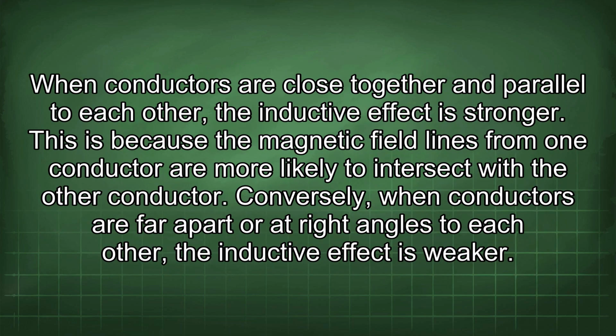When conductors are close together and parallel to each other, the inductive effect is stronger. This is because the magnetic field lines from one conductor are more likely to intersect with the other conductor. Conversely, when conductors are far apart or at right angles to each other, the inductive effect is weaker.